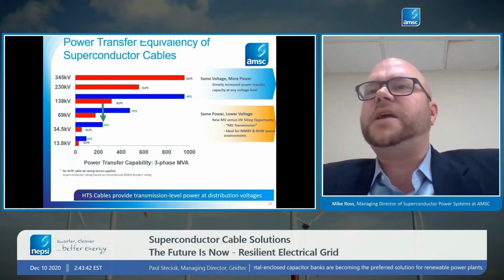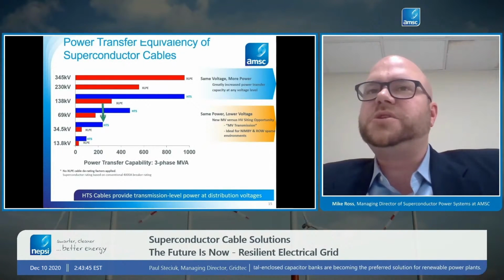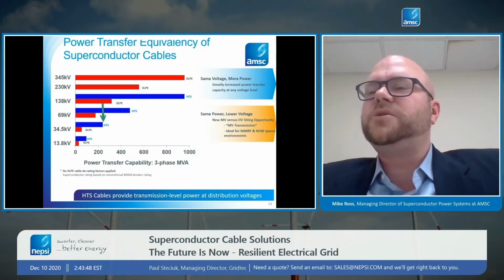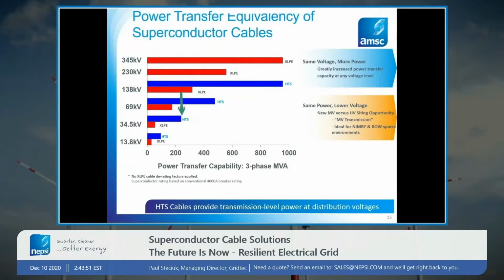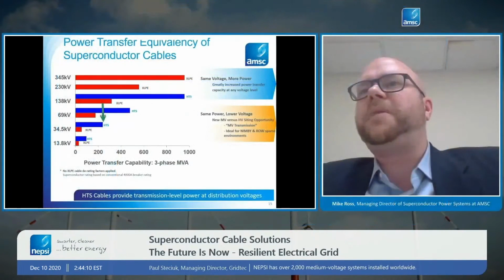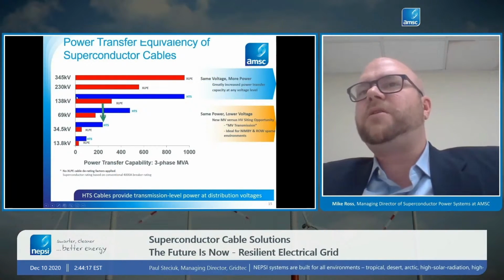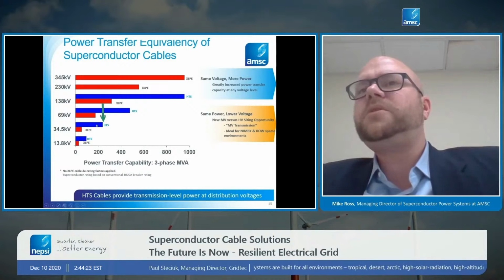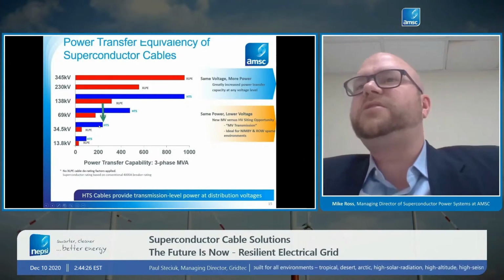So talking about applications. What is the value of this technology to utilities? And the main value is, again, this power density. And so at a given voltage level, say you have a 138 kV superconductor cable, we already talked about how that can carry about 4 times as much power as conventional technology. The typical cables that people install today are called XLPE cables, or extruded dielectric cables. So we can do about 4 times the power at a given voltage level. But where we really see value is being able to move the same amount of power that a transmission voltage cable can move at distribution voltages. So we can lower the voltage, but still have the same power.